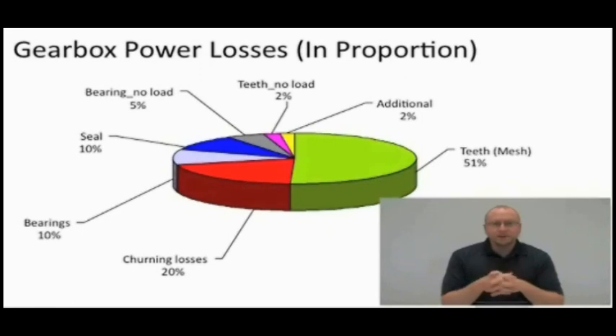Bearing losses can be minimized a little bit by using low friction bearings, but more importantly, the proper amount of lubrication. If you put too much lubrication, too much grease in a bearing, you're going to make it really inefficient. Bearings need the correct amount of lubrication. A high-speed bearing should be 1/3 full, while a low-speed bearing like your output bearing on a gearbox should be approximately halfway full of grease. So those are a couple ways you can minimize your seal and bearing loss.